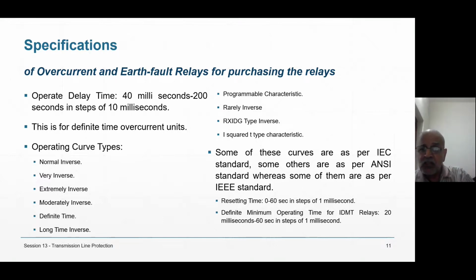Some of these curves are as per IEC, some are as per ANSI, and some are as per IEEE, because for different standards there are some variations in the formula of time of operation. So totally 17 or more curves are given by a single relay, costing about 1,30,000. Overcurrent relay. Induction motor relay is about 1.75 lakhs. Generator relay is roughly 2 lakhs. Very costly, but giving many facilities.